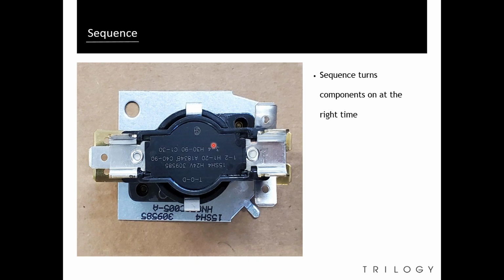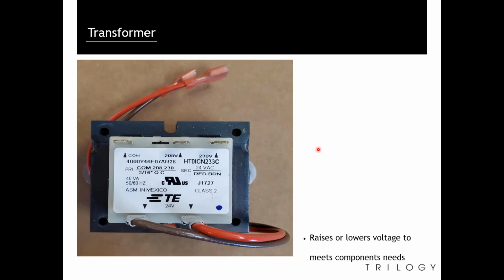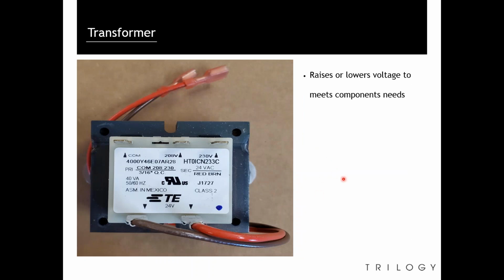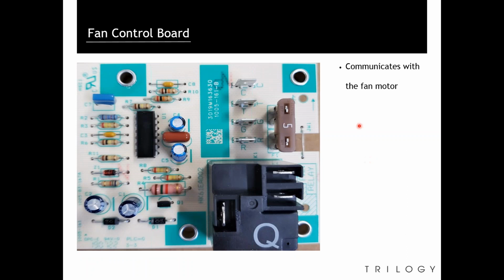This is a sequencer. The sequencer turns components on at the right time. It activates each phase of operation of the air handler, electric strips, fan motor in a sequence. Our transformer raises or lowers voltage to meet components' needs. 240 comes in, it then breaks it down to 120 or 24 volts, again, whatever components need.